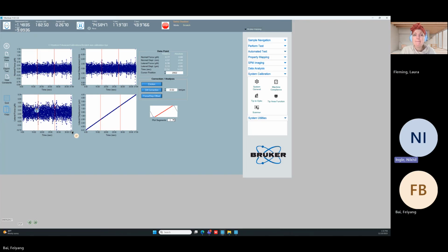I have one question. Do we need to normalize this or reduce this noise? I'm not sure how you would normalize it. I guess normalize means will it add to the error in your final calculation? The noise will, yes. Your system, like we talked about, is different from the 950. The anti-vibration system is completely different, so it does have a much higher noise floor than your 950. And yes, that may or may not impact your measurements; it may be present.